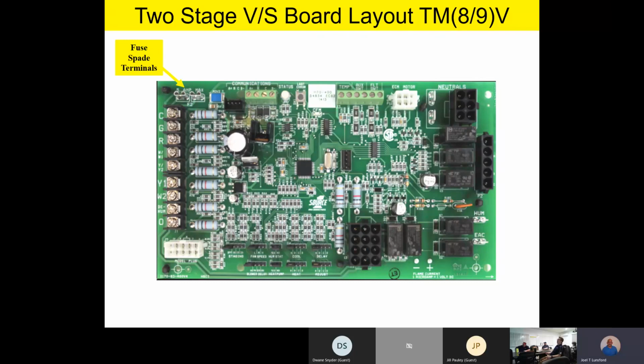If you had some 24 volt accessories that were pulling a little bit higher amperage. As we move around the board, we see we have some communication screw terminals. So this is pretty cool as well. This is a variable speed blower control, but this control board is also compatible with a 4-wire communicating system. So let's say, for instance, you've got a 19 SEER unit outside that you want to go 4-wire communicating, or maybe you don't have enough wires behind the wall. So this is a really slick little upgrade.